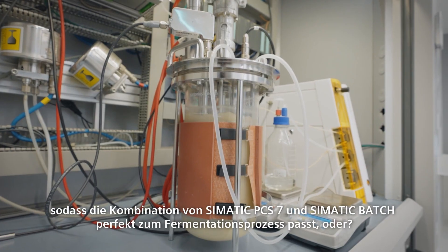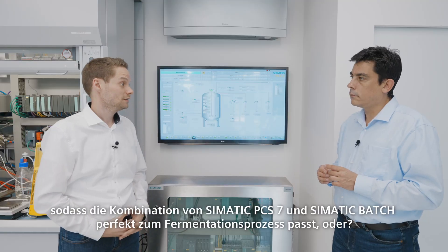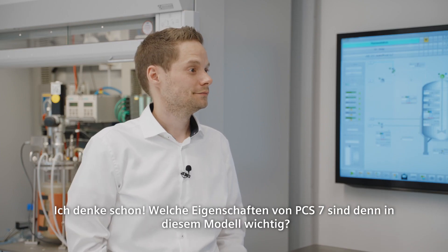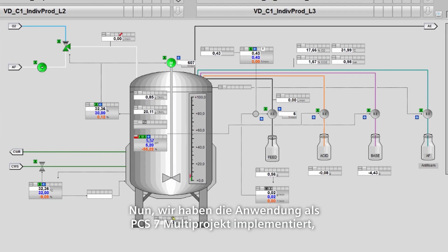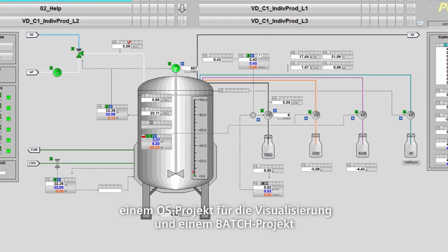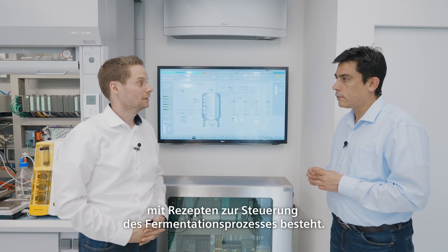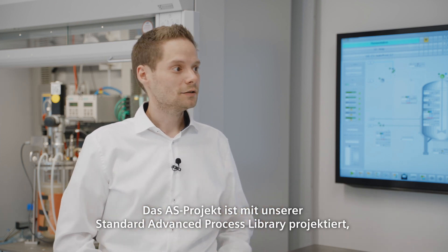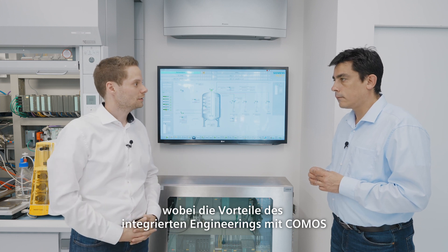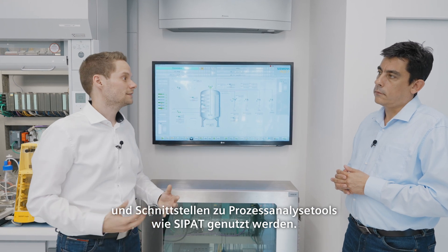The combination of SIMATIC PCS7 and SIMATIC Batch is the perfect fit for the fermentation process. We implemented the application as a PCS7 multi-project, which consists of an AS project for the user program, an OS project for the visualization, and a Batch project with recipes for controlling the fermentation process. The AS project is engineered with our standard advanced process library, using the advantages of integrated engineering with COMOS and interfaces to process analytic tools like SIPAT.